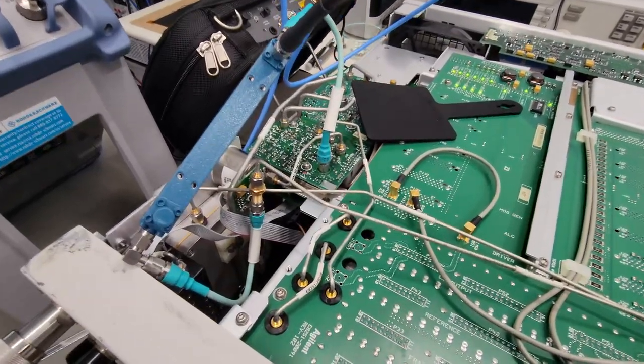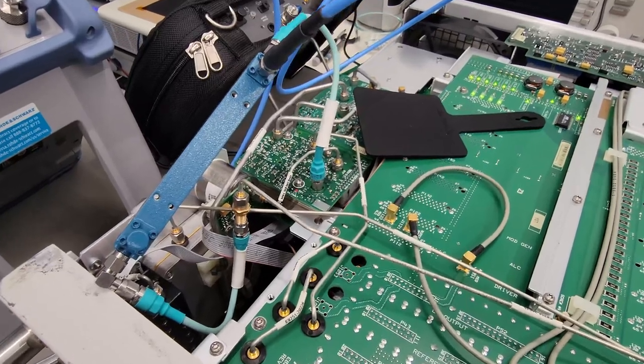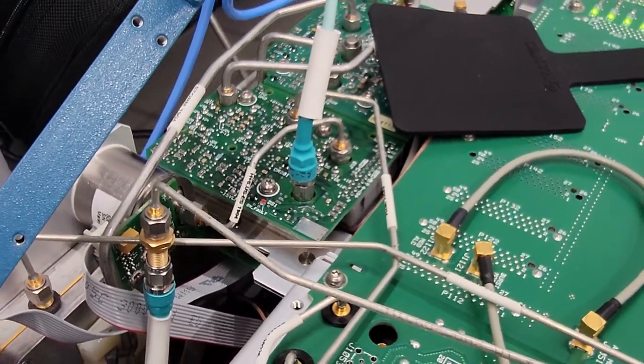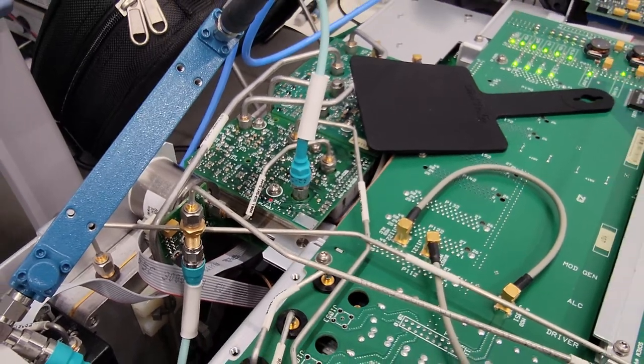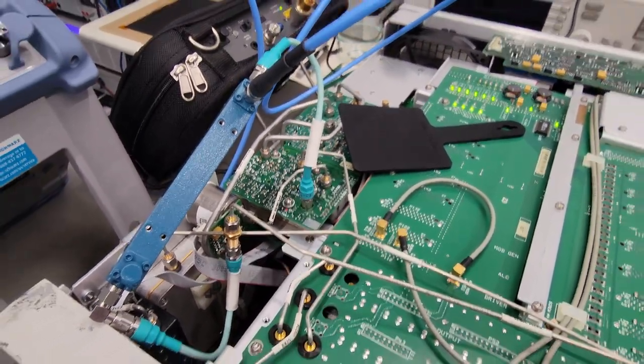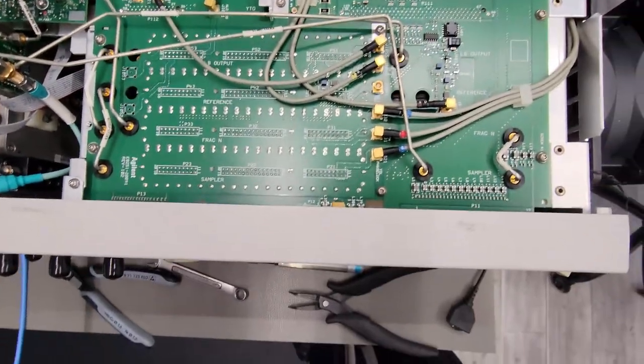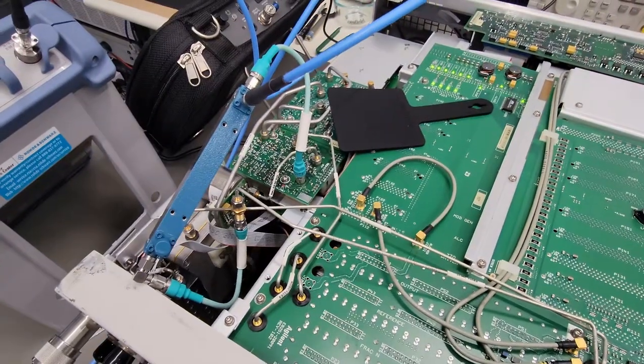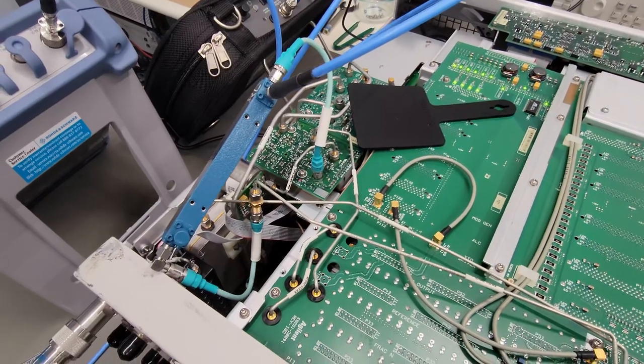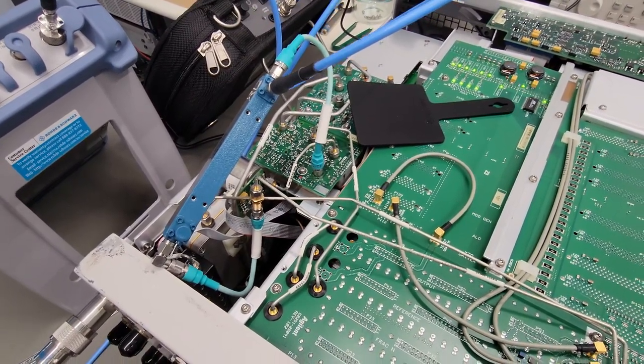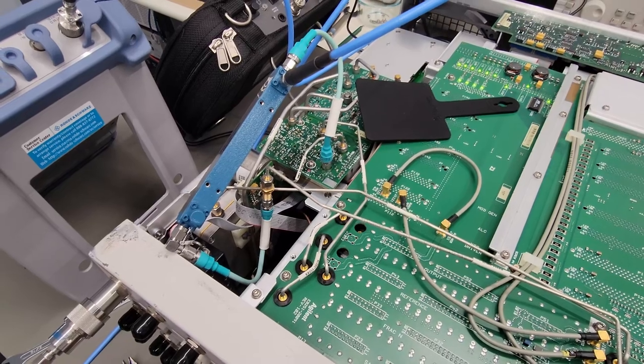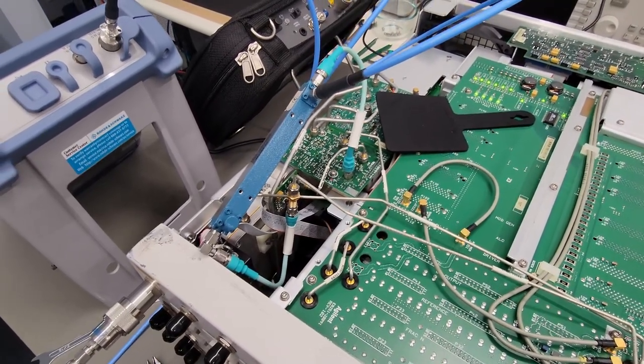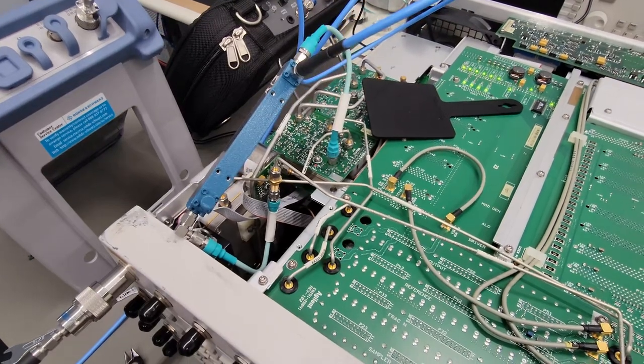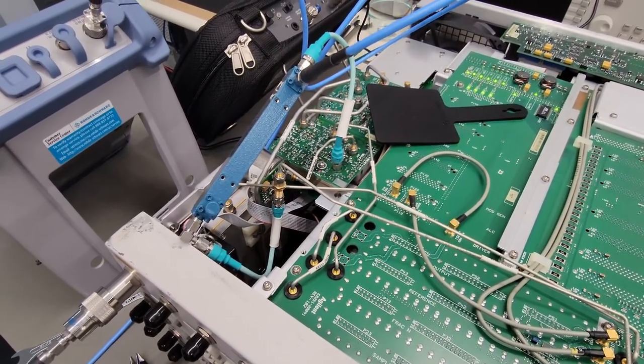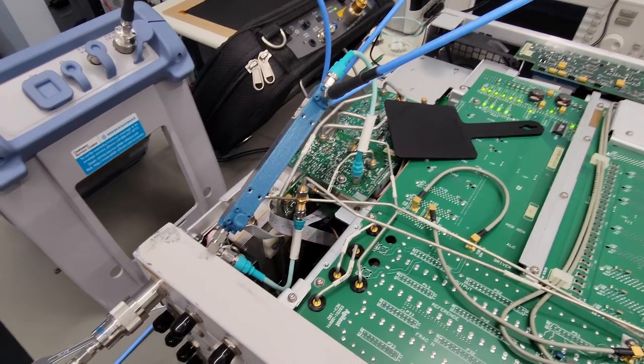Okay, so here's our second test setup. We've got our directional coupler again. And now we're looking at the output from J1 of the A29 20 GHz doubler into, I believe, the sampler here. According to the service manual, this signal should be between 3.2 to 10 GHz. It's directly coupled off of the YIG input, and it should be greater than or equal to minus 7 dBm. And there is an amplifier inside of the 20 GHz doubler to boost the coupled signal. So let's see if that signal is within spec.